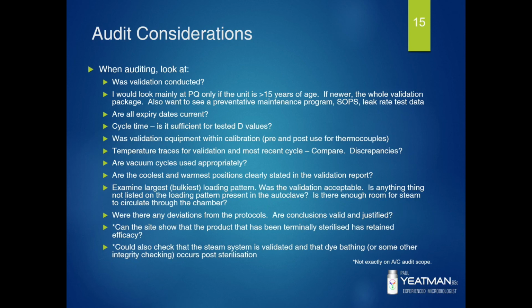A couple of things that are not quite on your audit scope of the autoclave specifically, but you want to look at in the grand scheme of production and autoclaves and everything, is can the site show that product that has been terminally sterilised has retained efficacy. So you filled your product, you've autoclaved it and killed off any, say, pharmacological effect. That's not good because the product doesn't do what it's advertised to do. So you want to make sure that your sterilisation doesn't actually affect the product.